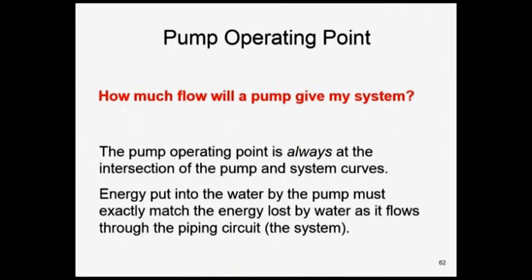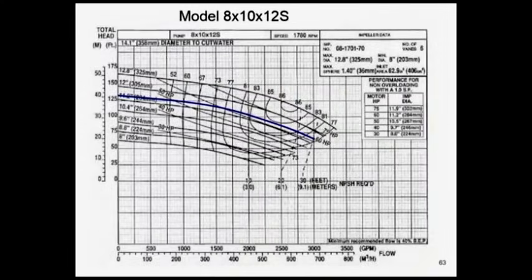And a very simple statement to you engineers. Remember the first law of thermo? Energy in is energy out. The energy you put in something, it's got to come out somewhere. So from a pumping standpoint, and here's a little pump curve, the pump impeller line, this pump itself, puts energy into the system. The system curve takes energy out.